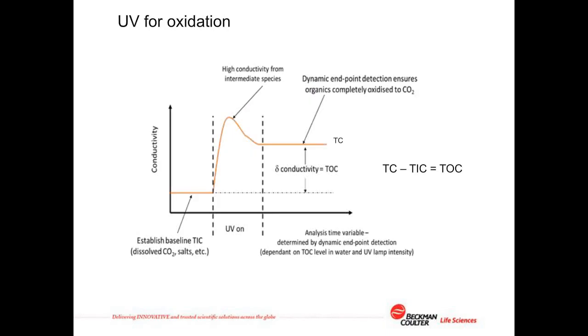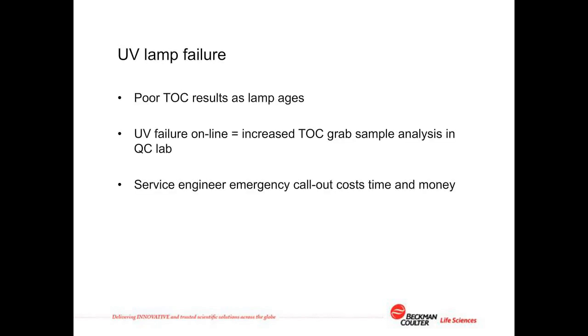As I discussed earlier, pharmaceutical-grade TOC analyzers rely on ultraviolet light to oxidize the organic molecule to release the carbon dioxide for TOC analysis. Total carbon minus total inorganic carbon equals total organic carbon. However, as the UV lamp inside the TOC analyzer ages, the intensity of UV light output reduces, and this can result in poor TOC analysis, and certainly in TOC analyzers with continuous flow and fixed oxidization time.